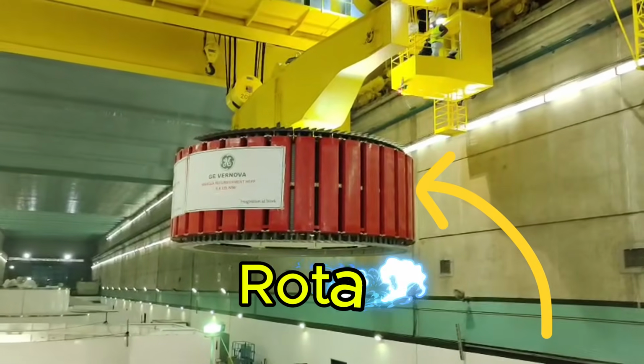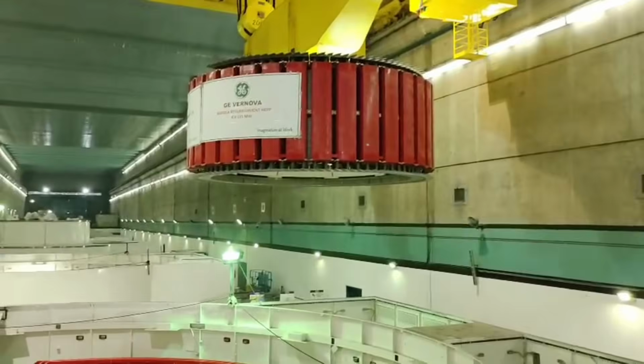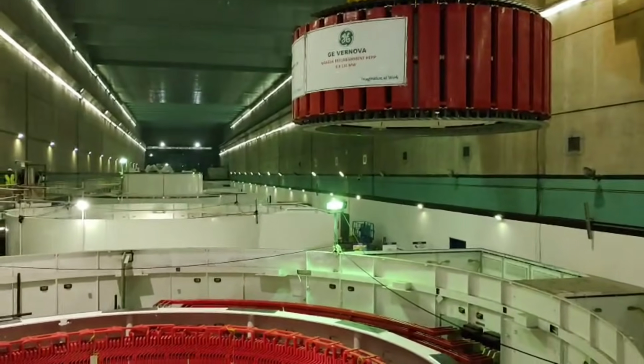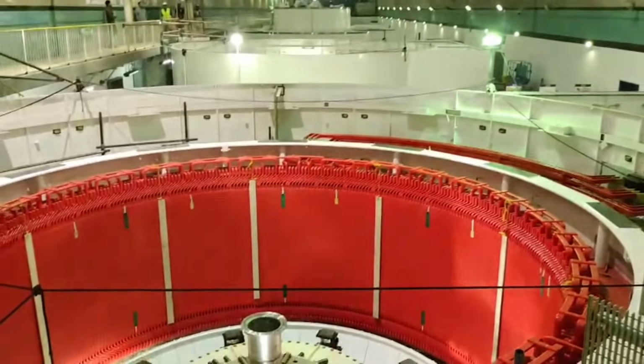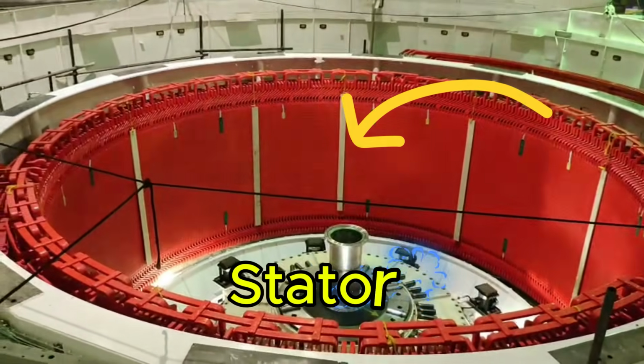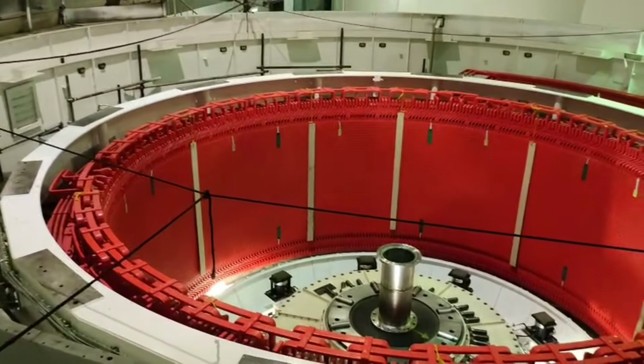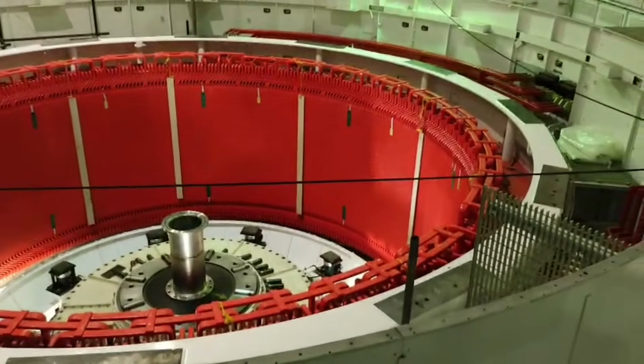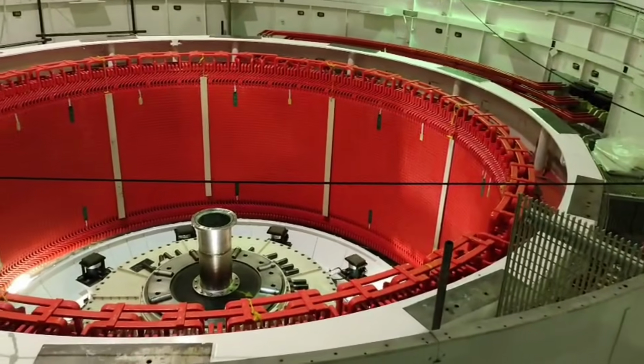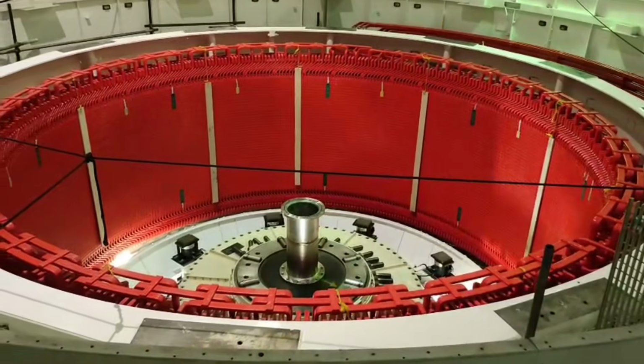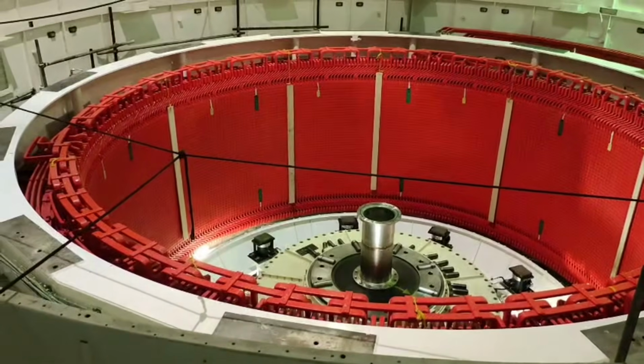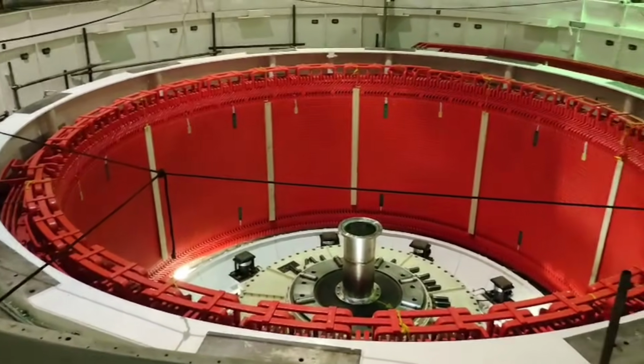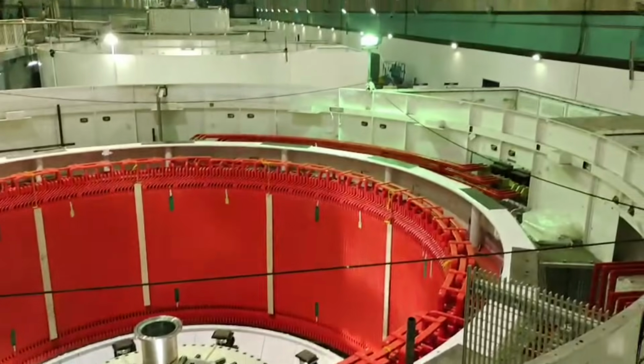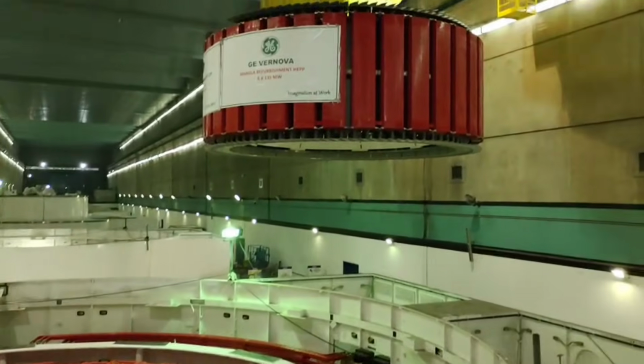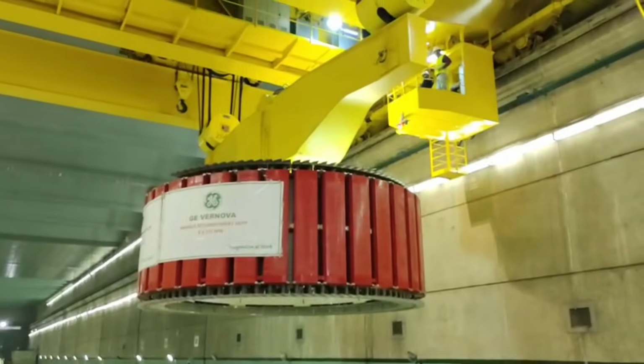The rotor is the massive rotating section connected directly to the turbine shaft. Surrounding it is the stator, the stationary outer section packed with huge copper windings. Think of the rotor like a giant spinning electromagnet. As it rotates inside the stator, its magnetic field cuts across the winding and electricity is born. But here's the catch: that magnetic field does not exist naturally. It must be created using a DC current.